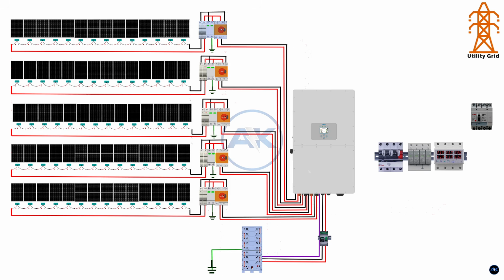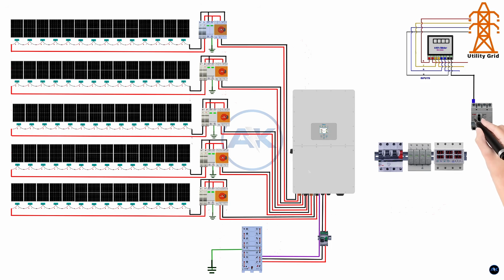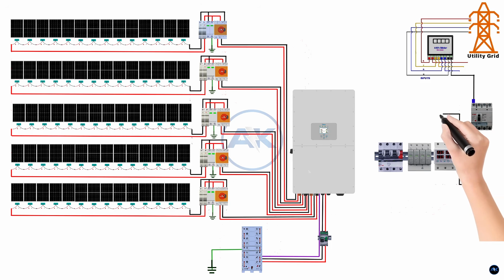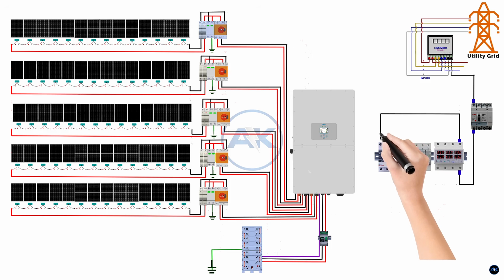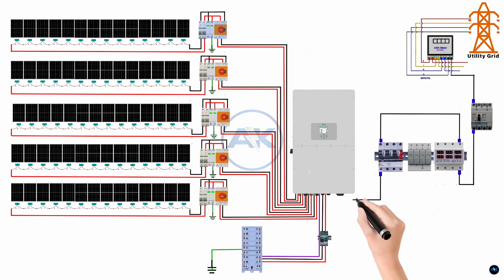We begin with the energy meter connection. The three-phase energy meter is installed on the main incoming grid supply before the inverter. Its purpose is to measure grid power flow accurately, so the inverter can control zero export. Connect grid phase L1, L2, and L3 from the utility supply to the corresponding input terminals of the energy meter. Connect the neutral wire to the meter's neutral terminal and the ground wire to the grounding bar.